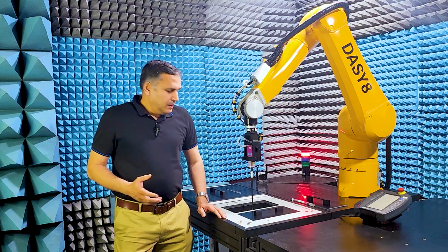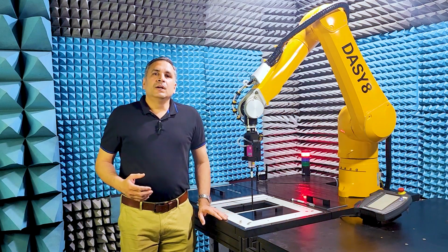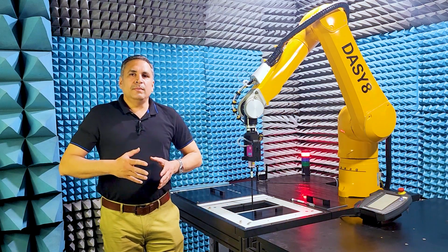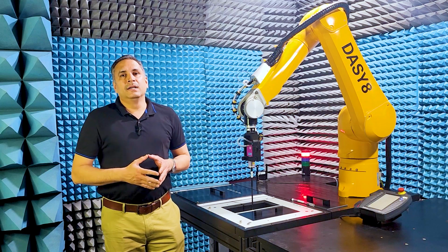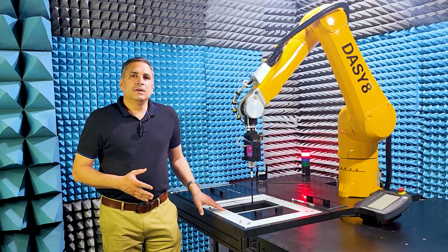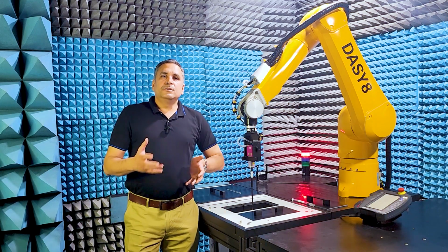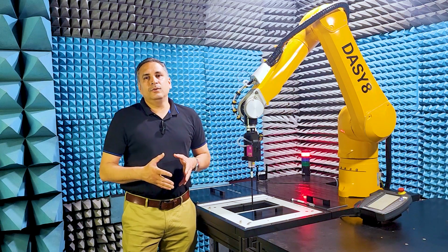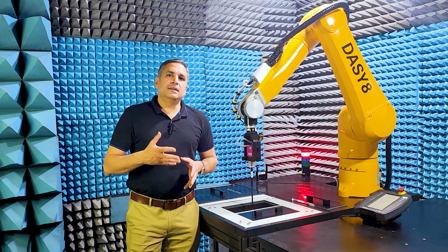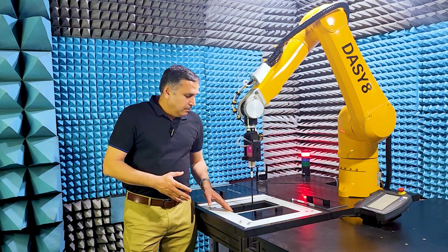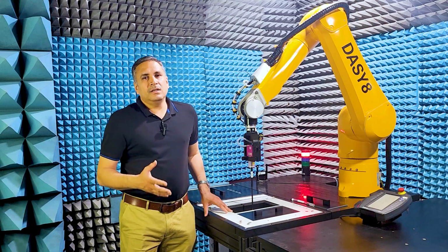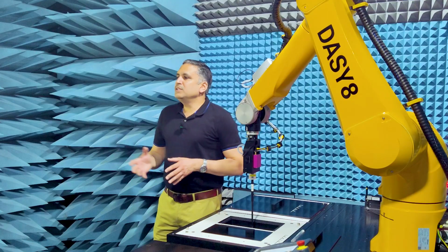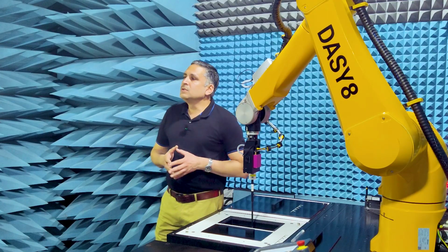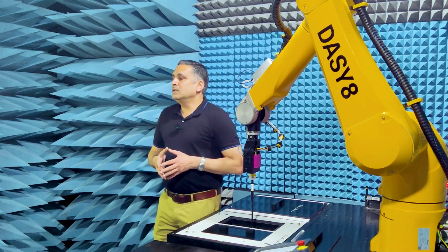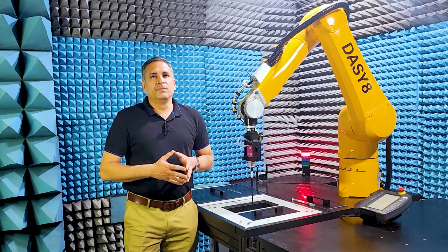The APD module, hardware and software are specially optimized for maximum sensitivity and measurement in high field gradients. While the probe is broadband and can be used from 10 to 45 GHz after the necessary calibrations, the phantom and liquid combinations are band specific. SPEAG mentioned that new phantoms will be added to cover other bands in future releases.